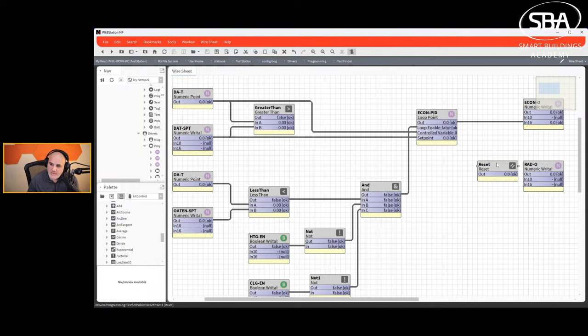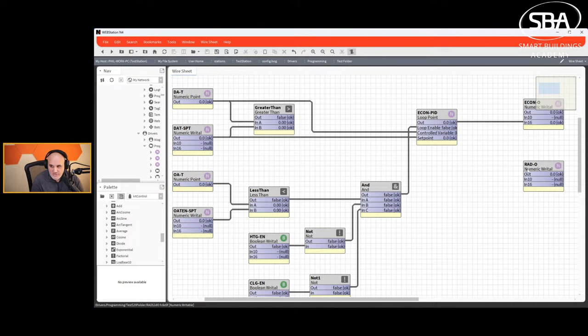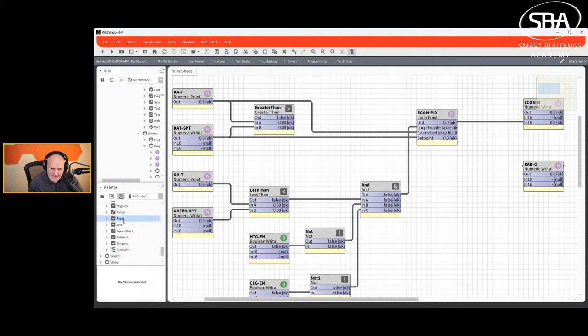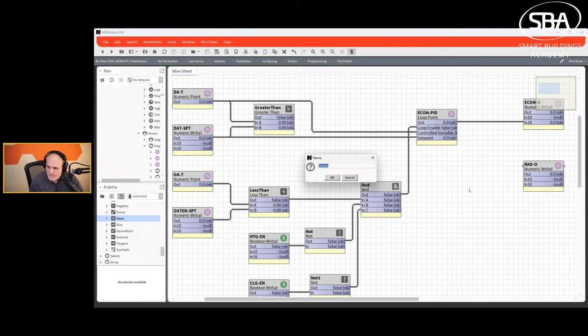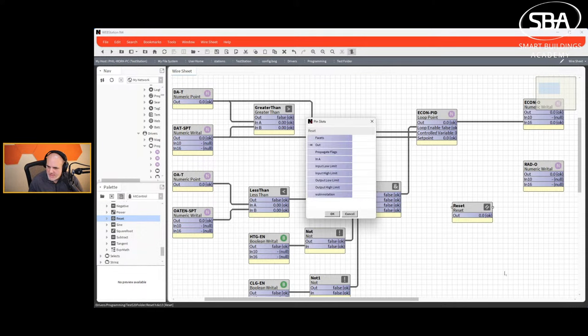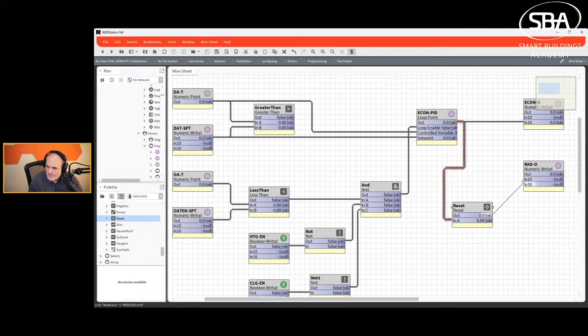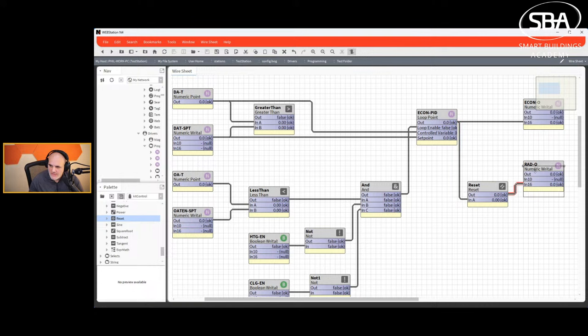For the economizer and return air damper, they need to be inverse of each other — I'll use a reset or span function: PID output at 0 maps to 100% for the return air damper and output at 100 maps to 0%. Alternatively, you can set one actuator to rotate clockwise and the other counterclockwise on a 0-10V signal, but I prefer to handle it in logic. So the PID output feeds both the economizer and the return air damper output with that reset applied.